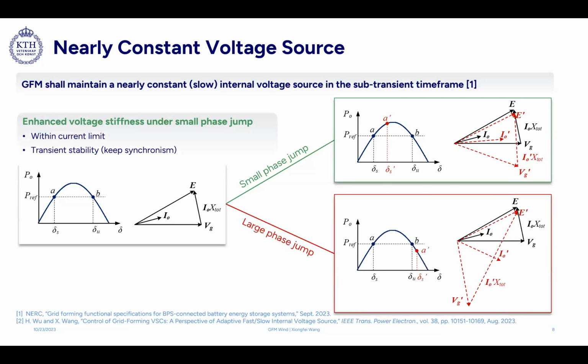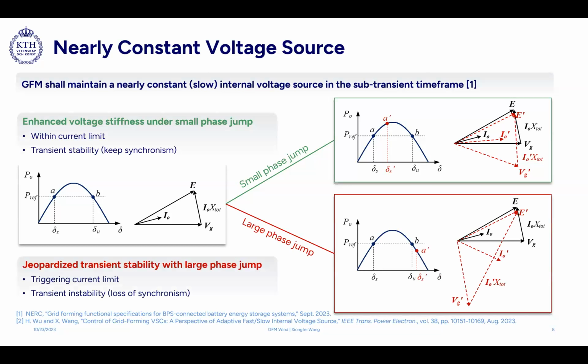However, if we consider a large phase jump, for example in the National Grid GC0137, a 60-degree phase jump is considered. With a large phase jump, if we still keep the internal voltage phasor nearly constant, then we will have a large phase angle difference between the grid voltage and the internal voltage. In this case, we can reach the current limit of the power converters, or we can jeopardize the transient stability. For example, in the power angle curve, we can easily enter the unstable region for the system. So this is just for general grid forming without considering the energy source limit.